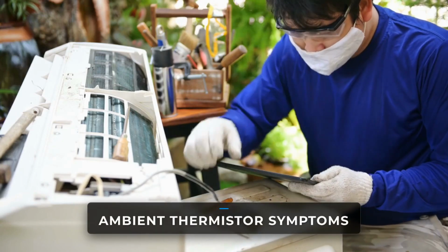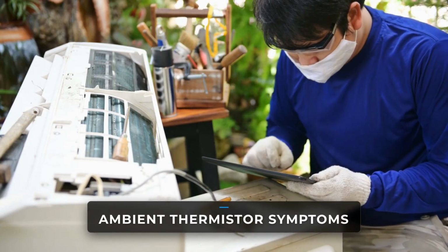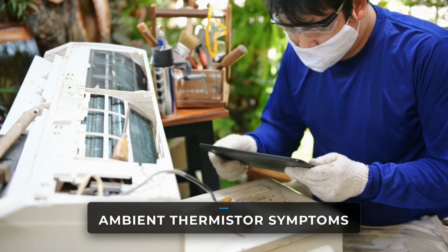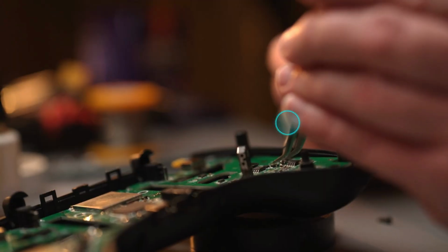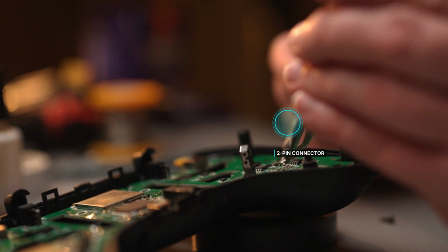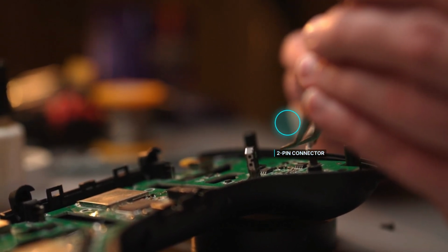First, let's talk about how your Hisense unit acts when this sensor goes bad. The room temperature sensor acts as the brain's thermometer. It tells the main PCB how cold your room is, so the inverter compressor knows whether to ramp up, slow down, or shut off. When it fails, three major things happen. Let's break them down so you can spot them immediately.